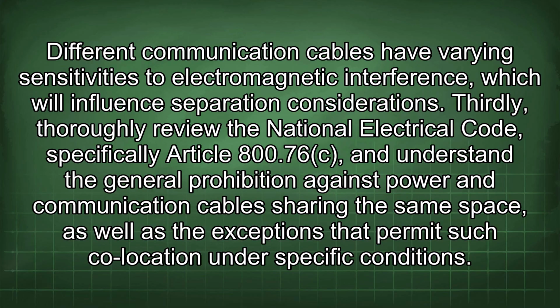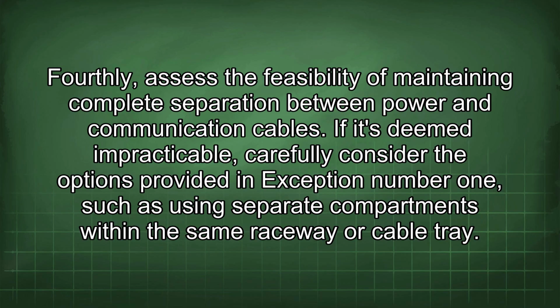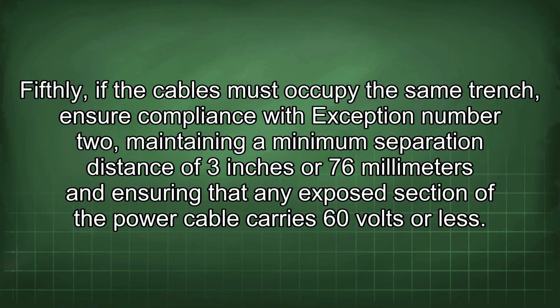Thirdly, thoroughly review the National Electrical Code, specifically Article 800.76, and understand the general prohibition against power and communication cables sharing the same space, as well as the exceptions that permit such co-location under specific conditions. Fourthly, assess the feasibility of maintaining complete separation between power and communication cables. If it's deemed impracticable, carefully consider the options provided in exception number 1, such as using separate compartments within the same raceway or cable tray. Fifthly, if the cables must occupy the same trench, ensure compliance with exception number 2, maintaining a minimum separation distance of 3 inches or 76 mm and ensuring that any exposed section of the power cable carries 60 volts or less.